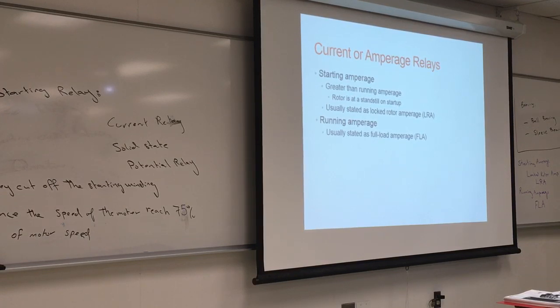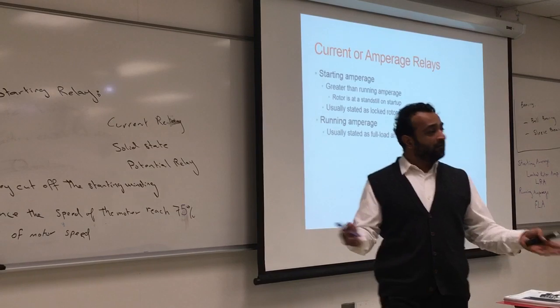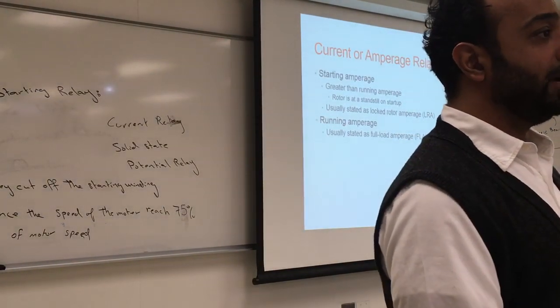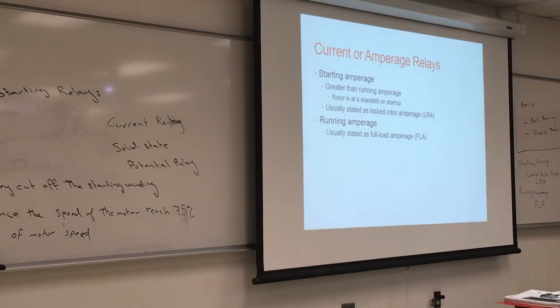Any questions about this? Motors are very important, because again, a lot of the components we have are motors. Just knowing how to diagnose motors is very important. And you're going to have to work with them a little bit more. So what if you went to a job and the FLA is not running at the right amperage? How do you check that? Check the capacitor. Check the wiring. If it's lower or higher? Let's take a case. You go there. You put your clip on and the amperage is higher. Something is wrong. Is it bearing? That's bad. Some obstruction. Try to go and clear it up. If it's still higher, then change the motor. Something is wrong with the motor. If it's too low, by a little bit, that's okay. If it's too low by a lot, that's not okay. Probably is not giving you the right output. What's a little bit? Ten percent.